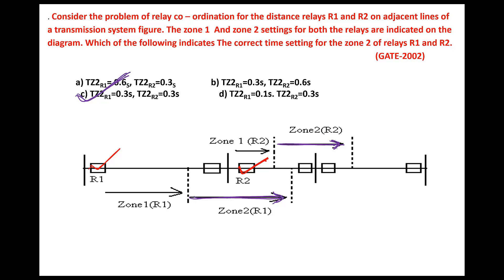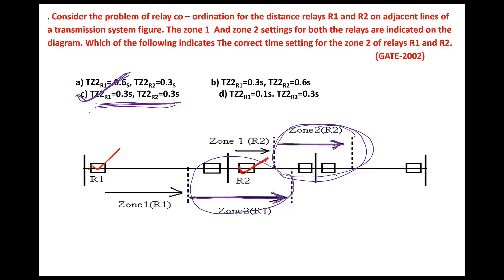Zone 2 region should have some time delay, and for relay R2 the zone 2 region should also have some time delay. Both time delays for zone 2 of relay R1 and R2 should be the same. If he had asked for zone 3 of relay R1 versus zone 2 of relay R2, there should be some discrimination and option A would have been right. Since he is asking zone 2 of R1 and R2, both should have the same time delay of 0.3 seconds.